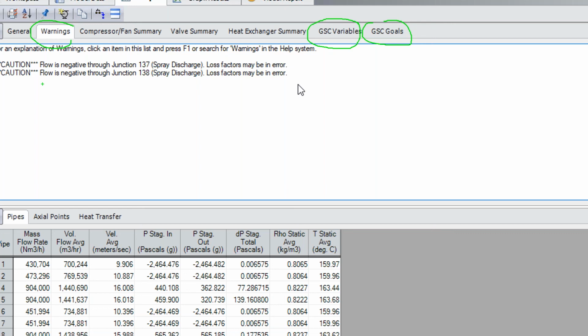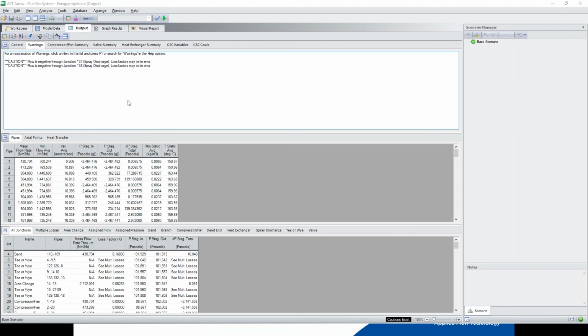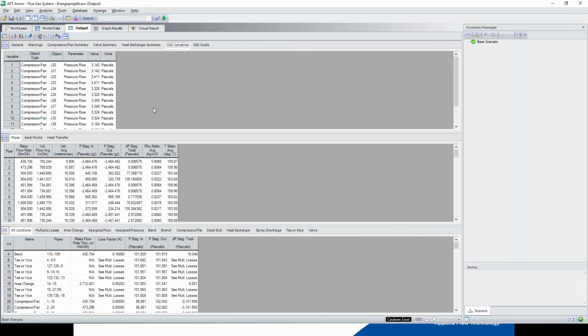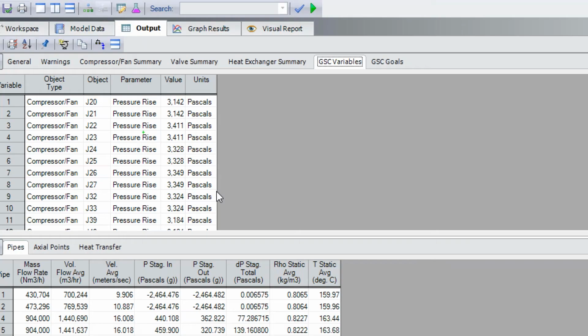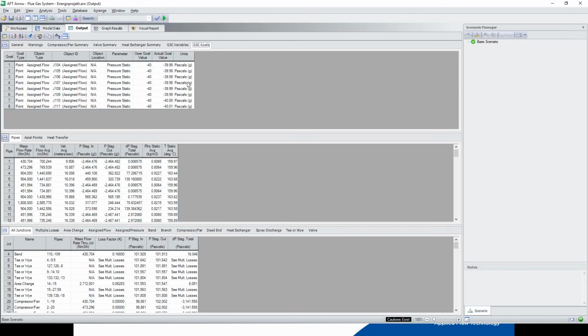So if we see the variables here, now we know the pressure rise required in each one of the fans to achieve the goals required. And each one of them is minus 40. In reality, we reach 39.98 Pascal. Then once you see that those are the conditions required to achieve the goals you want, you can create a disconnected scenario with the new variables and the achieved goals.